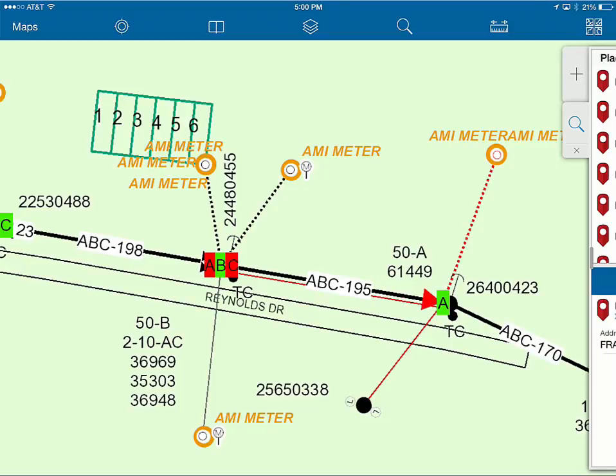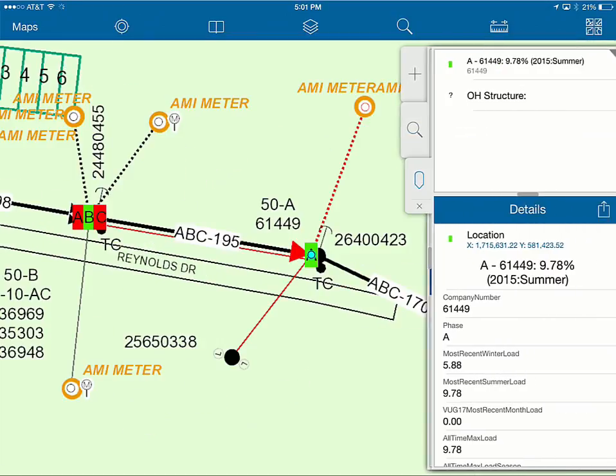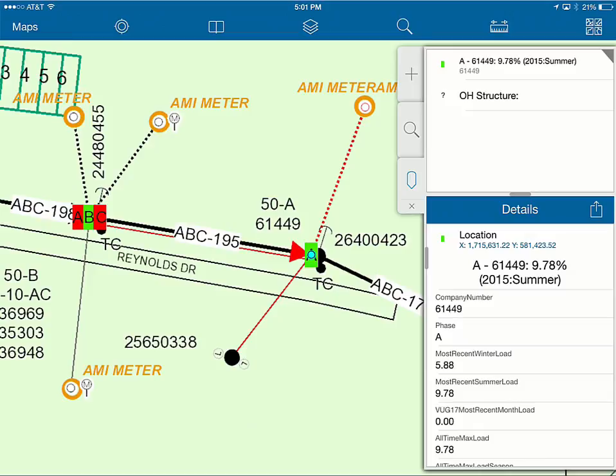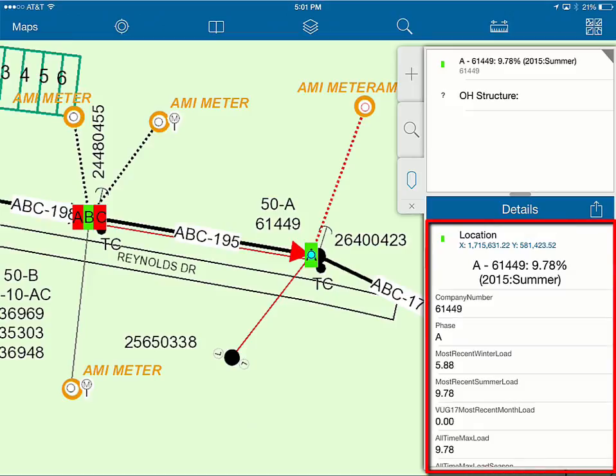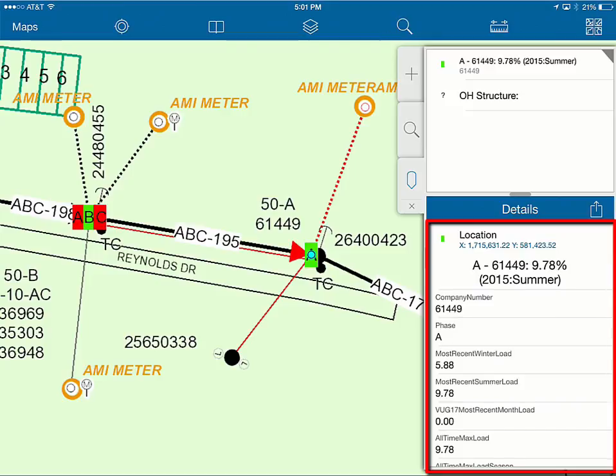One of the things we can tell directly here is how the transformer is loaded. We developed thematic map styling so that, based on the loading percentage, we can see how heavily loaded a transformer is. Field users can click on any individual reading to get the detail. For example, this A-phase transformer number 61449 is loaded at 9.78% — a very low load. The all-time max load was achieved in the summer of 2015, so there's really nothing to worry about on that one. If we were replacing this A-phase, we would definitely not worry about upsizing it.